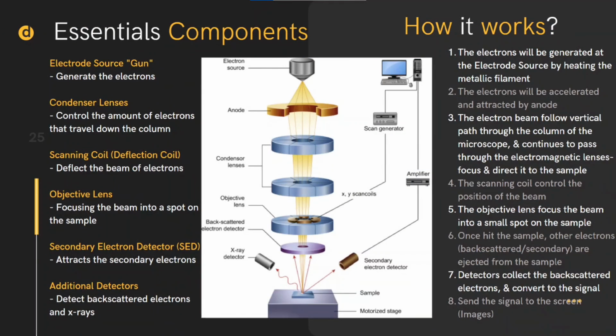So SEM contains some essential components. The first one is the electron source or electron gun that generates the electrons. The second one is the condenser lenses, which control the amount of electrons that travel down the column. The third one is the scanning coil, also known as the deflection coil. It deflects the beam of electrons. Next, the objective lenses, which focus the beam into a spot on the sample. And the secondary electron detector, or SED, which attracts secondary electrons. And the last one is the additional detectors, which detect the backscattered electrons and X-rays.